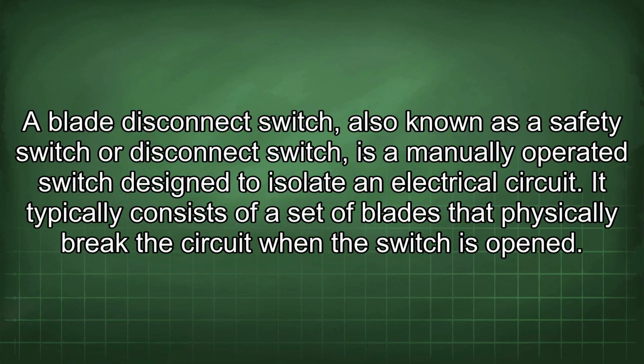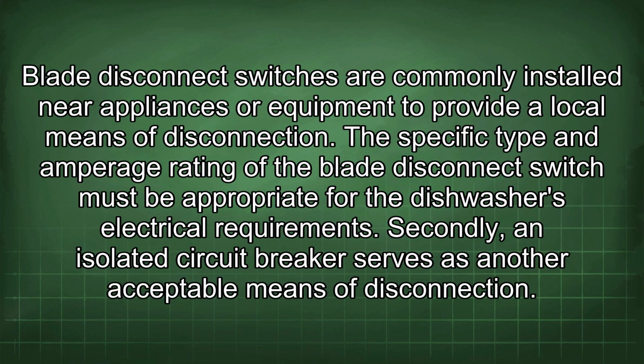A blade disconnect switch, also known as a safety switch or disconnect switch, is a manually operated switch designed to isolate an electrical circuit. It typically consists of a set of blades that physically break the circuit when the switch is opened. Blade disconnect switches are commonly installed near appliances or equipment to provide a local means of disconnection. The specific type and amperage rating of the blade disconnect switch must be appropriate for the dishwasher's electrical requirements.